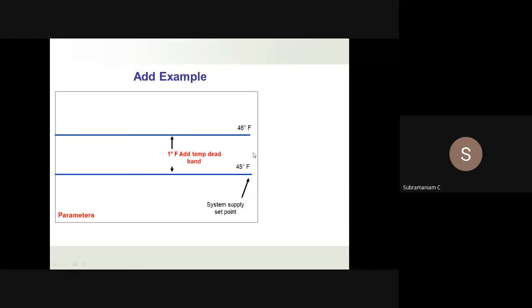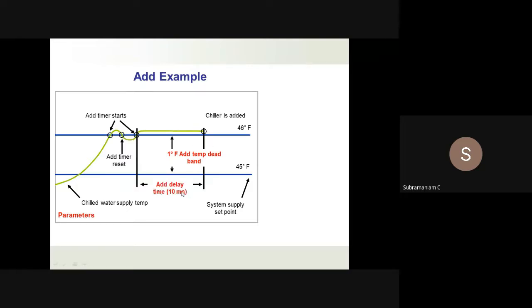For example, there are 5 chillers in a building. My set point at the header line to the air handling unit is 45 degrees Fahrenheit. For example, in the month of May at 9 o'clock or 10 o'clock in the morning, one chiller is running. As the sun starts coming and people start getting occupied, the chilled water temperature goes up. When do we add one more chiller? So this is my chilled water temperature, it keeps on going up. Now, if it stays there for a sufficiently long time, either 5 minutes or 10 minutes, or adjustable, then you add the chiller.